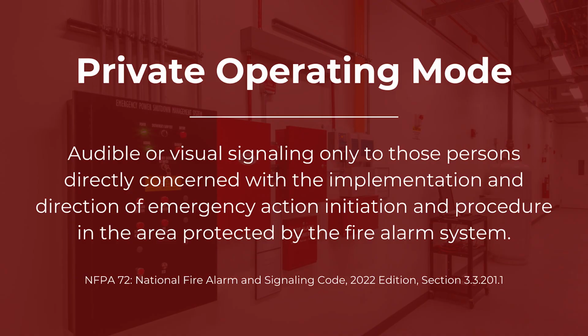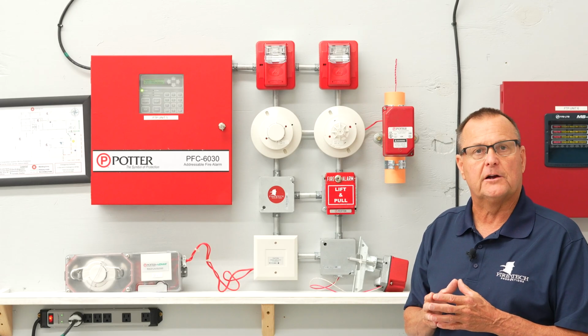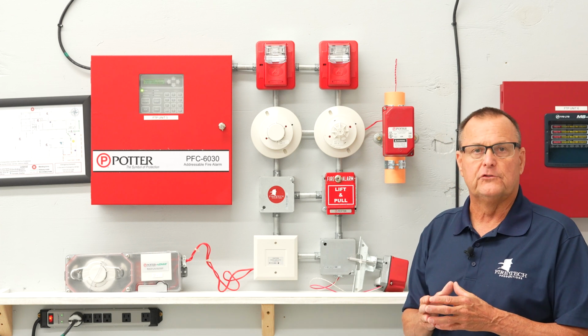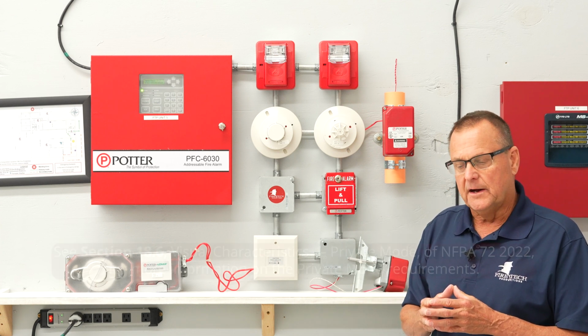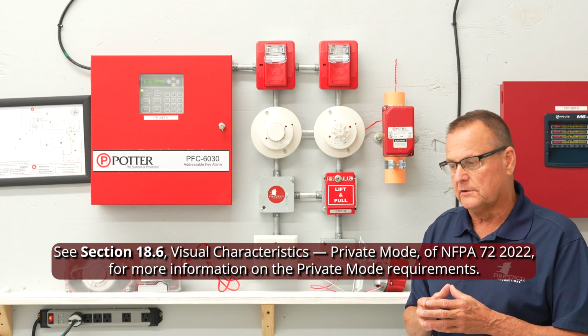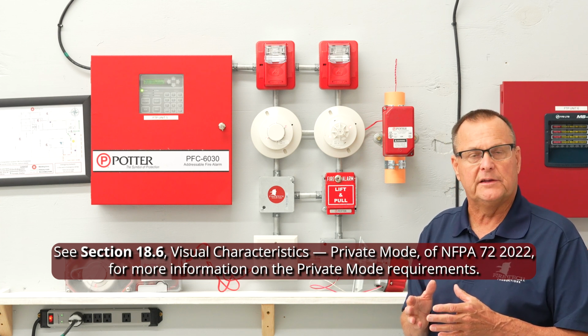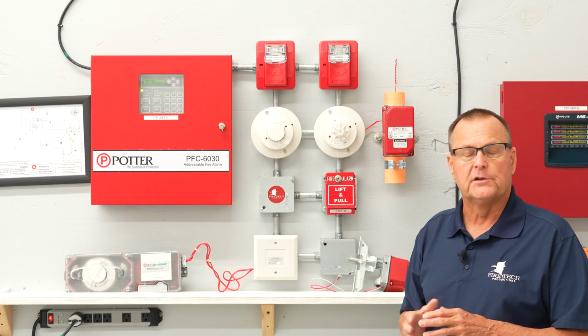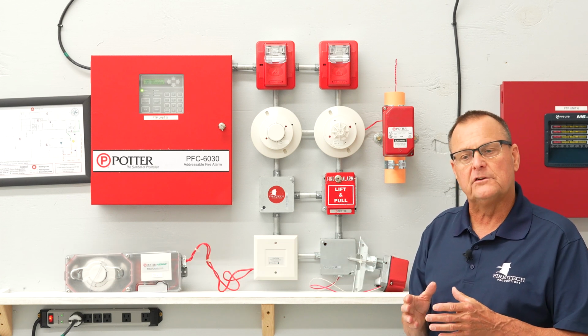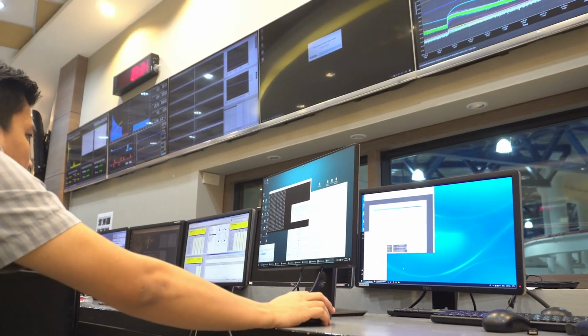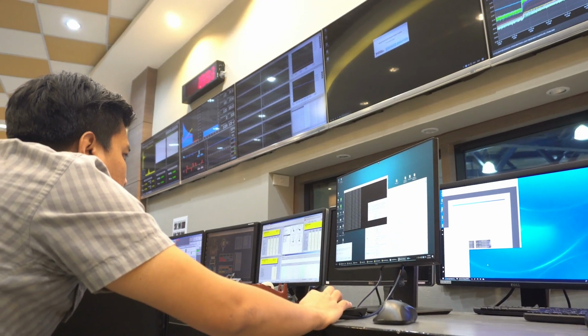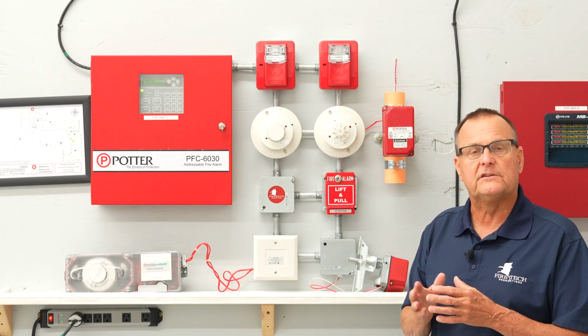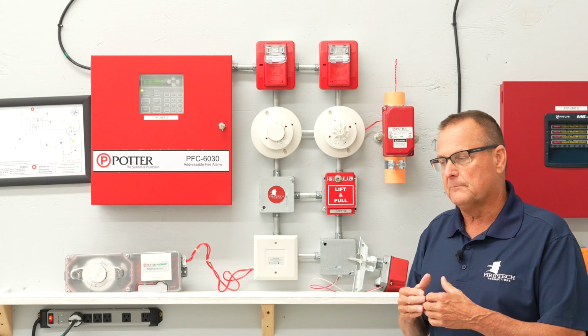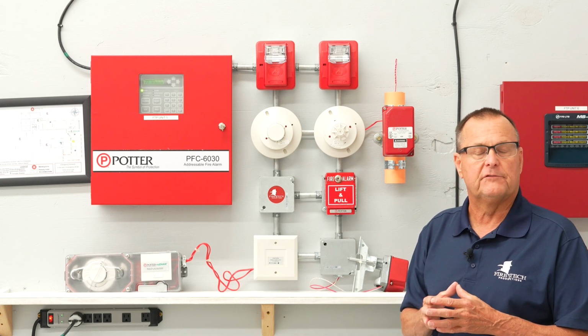Other buildings use what we call private mode signaling, where, one, you might not necessarily evacuate occupants from a building. You might, in healthcare for example, move those individuals into another protected area. And maybe the people in this particular environment aren't able to evacuate themselves due to health, age, or physical limitation. Private mode is intended to signal the trained personnel, whether security or nursing staff, or people like that within the occupancy, to take the appropriate actions to either move people to another area or to assist in evacuation of the building.